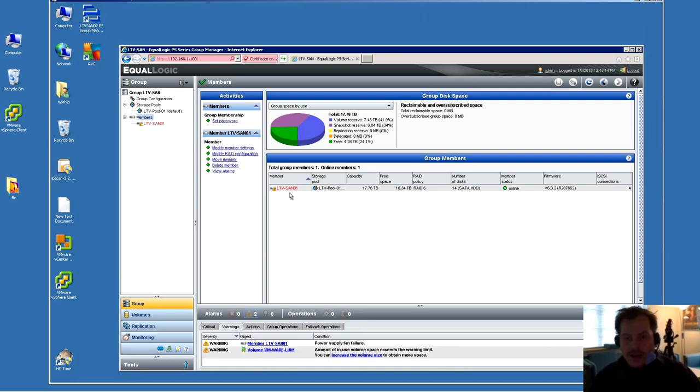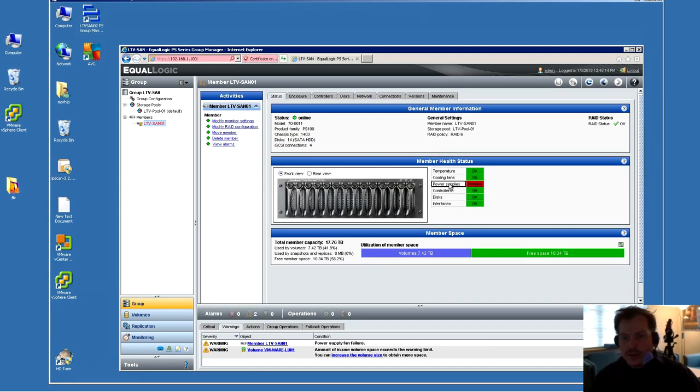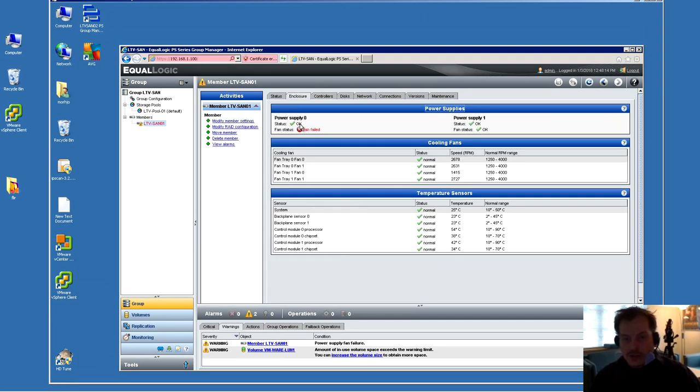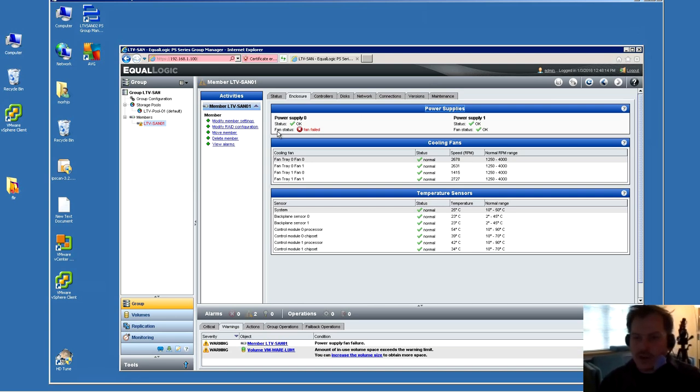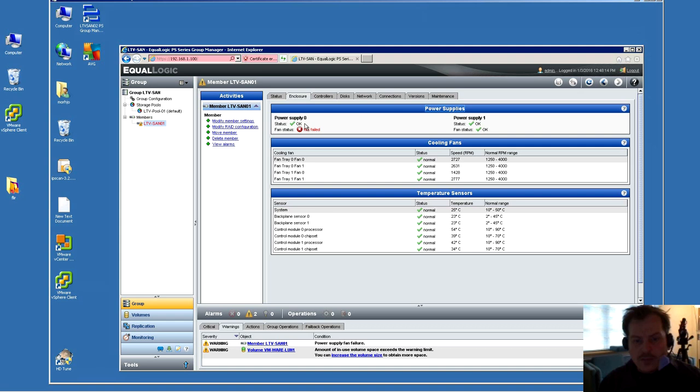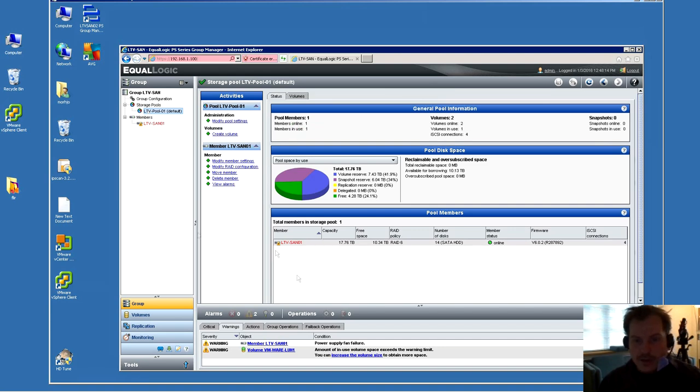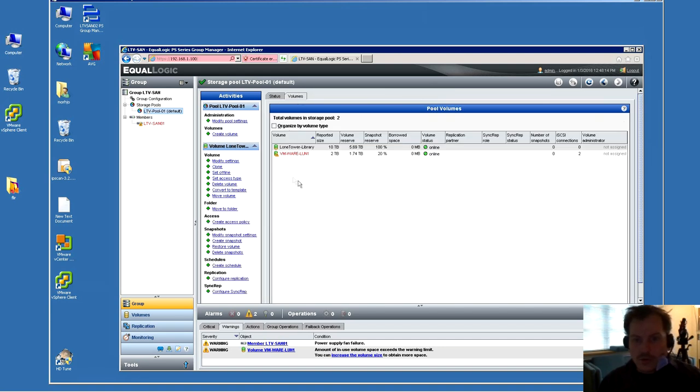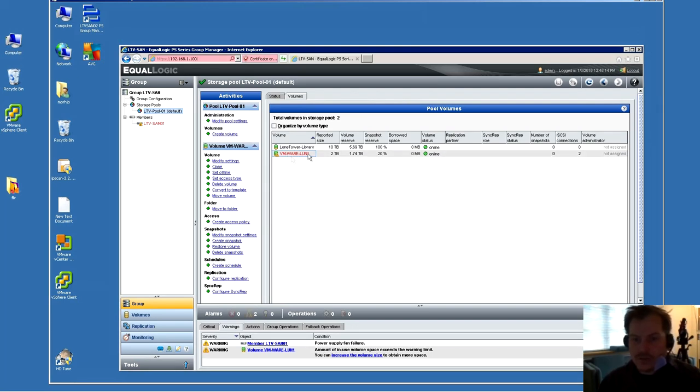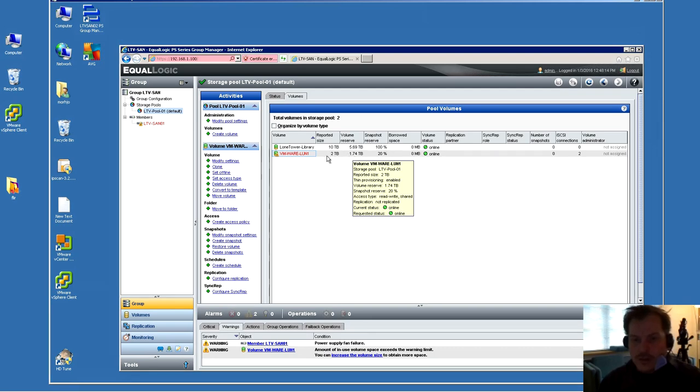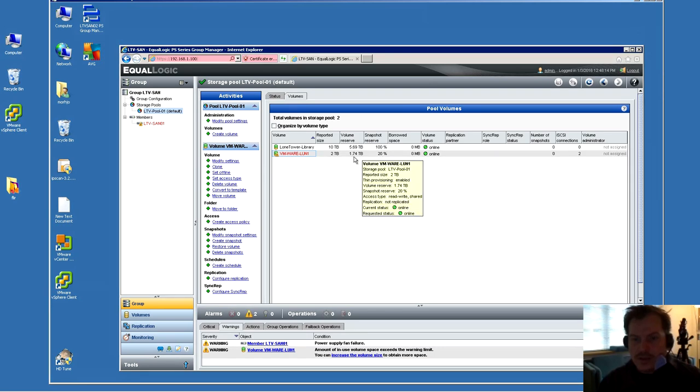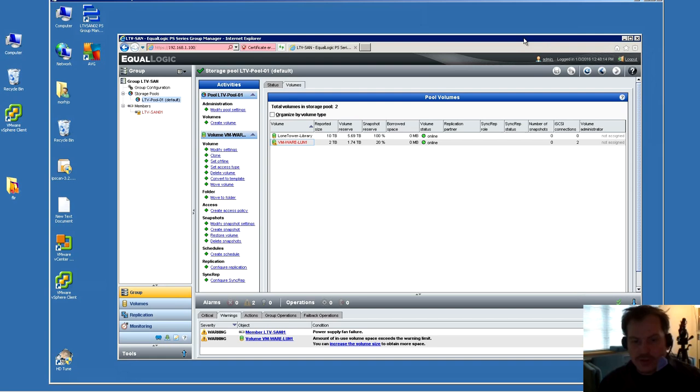And the web interface looks - it's very similar. I think it's the same, other thing that's just opened in a web interface. And let's see the error down here. Warning, almost amount of used. Okay, I'm actually running into some limitation here. That's all good, but I have another problem on this box, and it's the power supply. Power status is good, but it has a failed fan, so one of the fans in that power supply has stopped. So I think I might just go have a look at that too, to get that up and running. Take one of the power supplies from the spare and put it in bay number zero, if I can find that one. And then that should be good again.